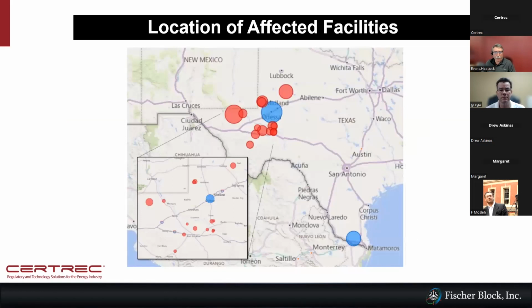For, again, the event, you can see the big blue dot is basically where the event was, of course, right there about Odessa. And then you can see the size of the bubble shows the size of the impact of loss of generation in the areas. You can see way down South Texas, due to the disturbance, that actually tripped a synchronous unit down south. The blue is the synchronous and the reds are the IBRs. And you can see how close they were all to Odessa.